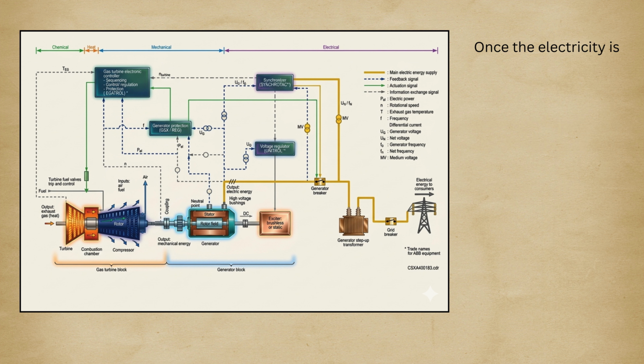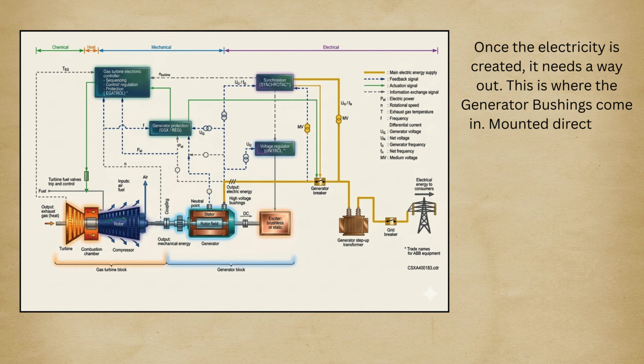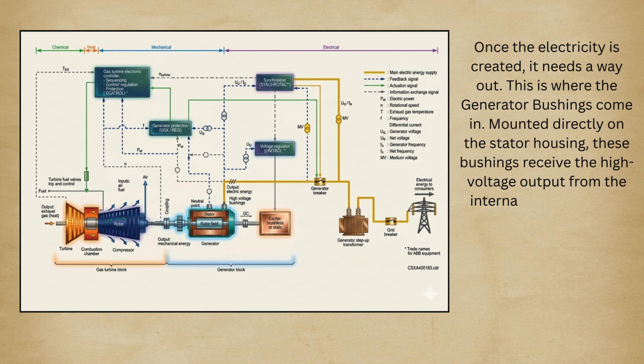Once the electricity is created, it needs a way out. This is where the generator bushings come in. Mounted directly on the stator housing, these bushings receive the high voltage output from the internal windings.